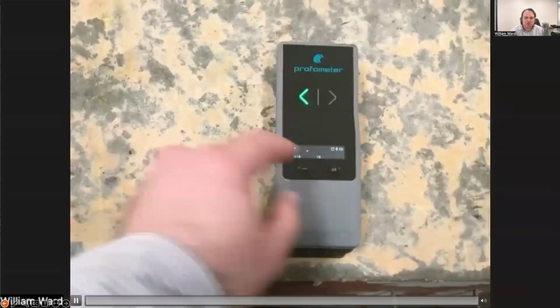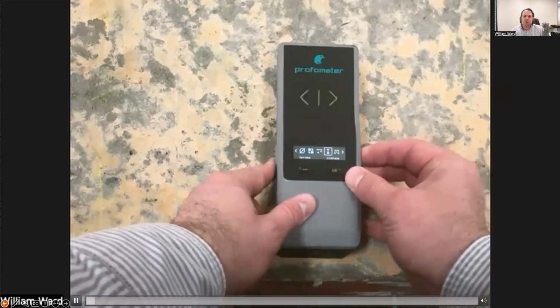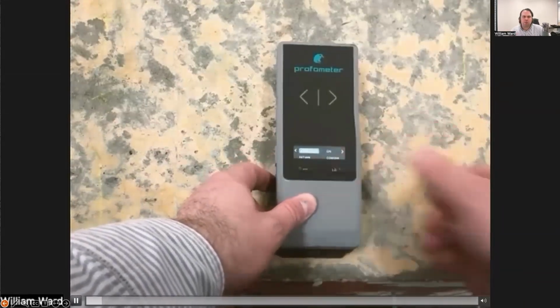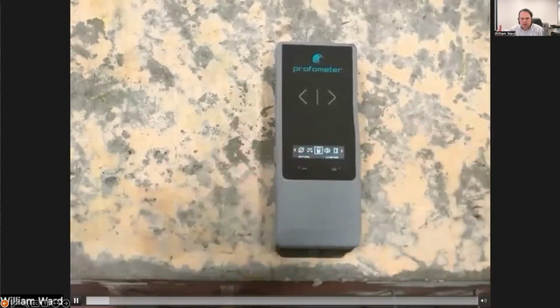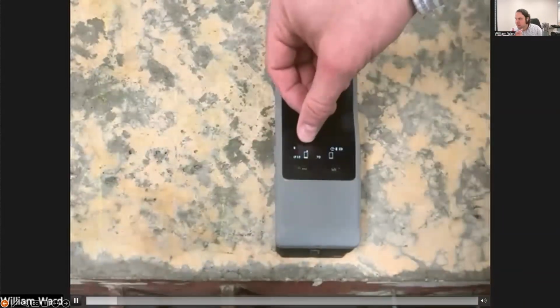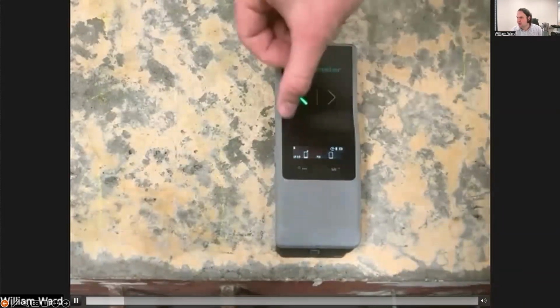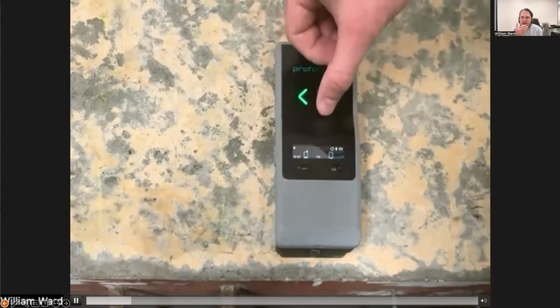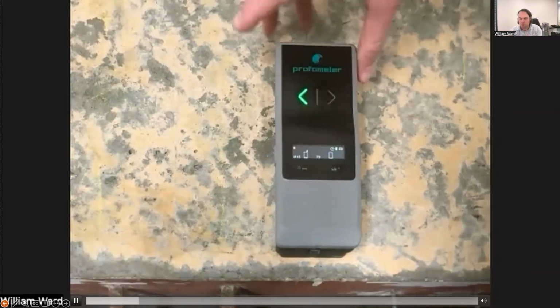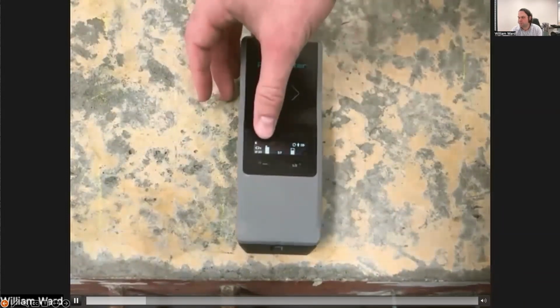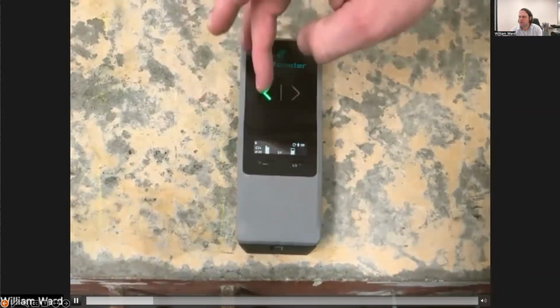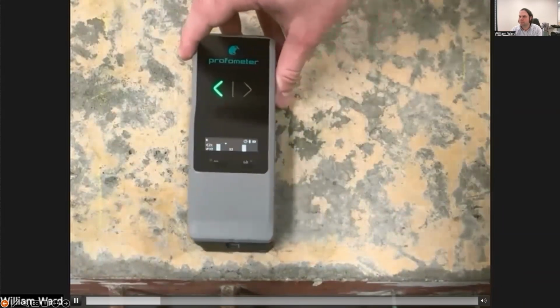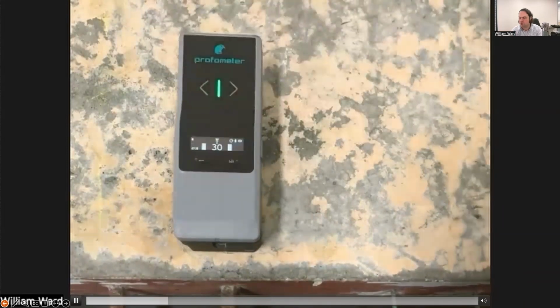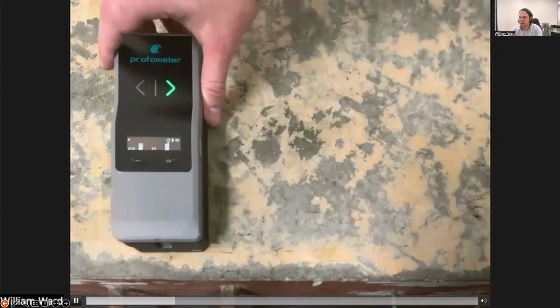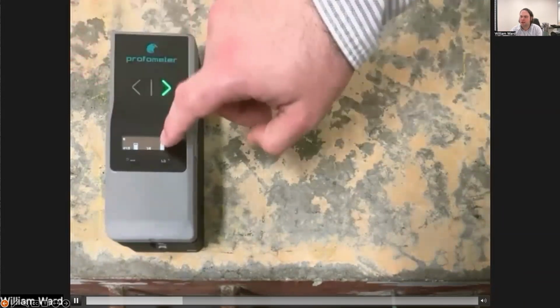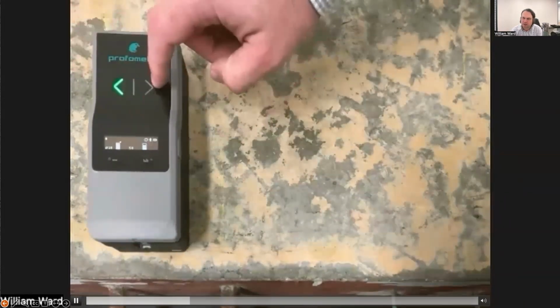So the final function I want to show for the PM8000 Lite operation is the new signal strength modes. And these are very useful where you've got complex layouts. So I showed you what we can do if we're in a line scan by sketching out the functionality. The signal strength bars, so we've got one on the left and one on the right, allow for similar operation where we don't have a line scan behavior. So this is showing the direct output of left coil and right coil. So as I approach a bar, left coil increases first. And then as I center on the bar, both of our coils are up and our normal centering behavior is shown. And then as I go to the midpoint, left coil drops, then left coil increases and right coil drops, and then we recenter on the middle.